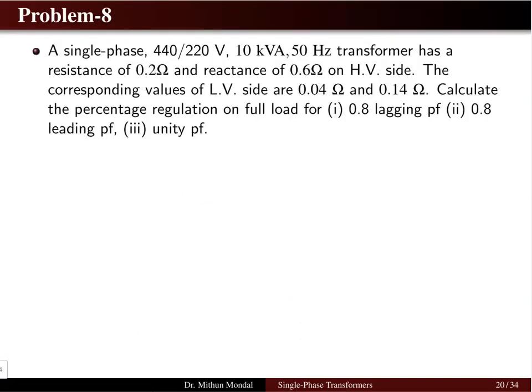So the problem number 8, where we have a single phase 440 by 220 volt 10 kVA 50 Hz transformer, the resistance of 0.2 ohm and reactance of 0.6 ohm are on the high voltage side. So high voltage side is basically 440 volt side. The corresponding values on the low voltage side is also given. So 220 volt side is also given. Calculate the percentage regulation on the full load side or the full load condition for 0.8 lagging power factor, 0.8 leading power factor and unity power factor. So under different power factor condition, we have to find the percentage regulation of the transformer.